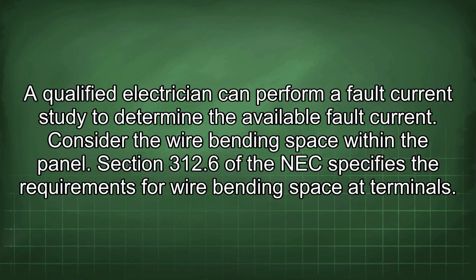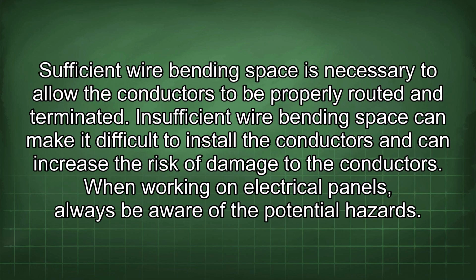Consider the wire bending space within the panel. Section 312.6 of the NEC specifies the requirements for wire bending space at terminals. Sufficient wire bending space is necessary to allow the conductors to be properly routed and terminated. Insufficient wire bending space can make it difficult to install the conductors and can increase the risk of damage to the conductors.